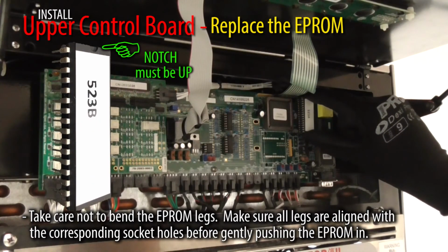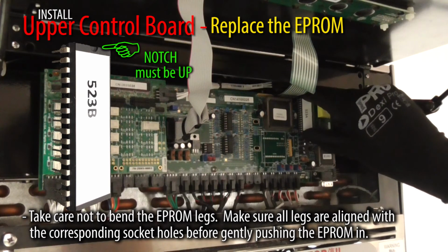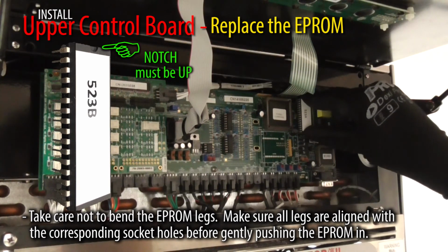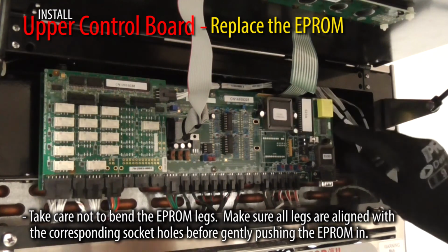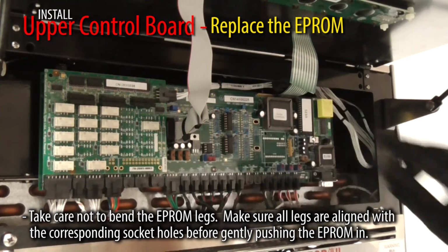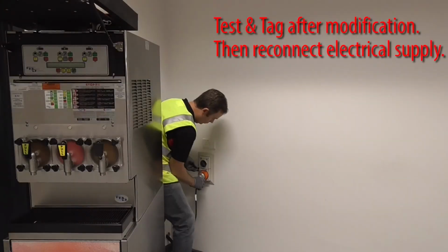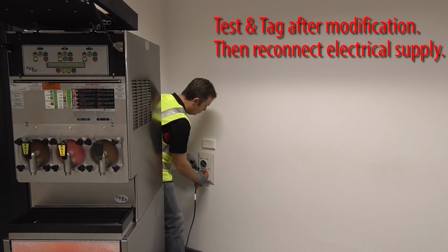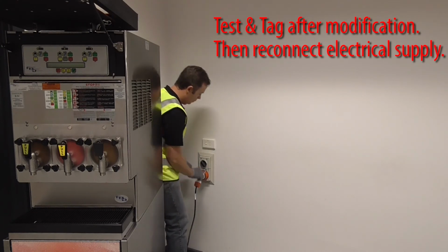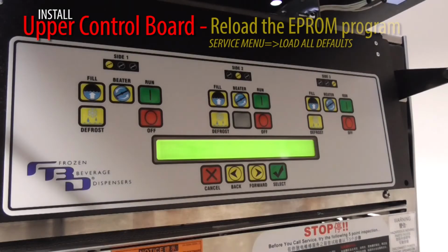Reinstall the EEPROM with the notch up and ensure all the legs are aligned with the corresponding holes before gently pushing the EEPROM in. With the upper control board install completed, test and tag the FBD and then reconnect the electrical supply.